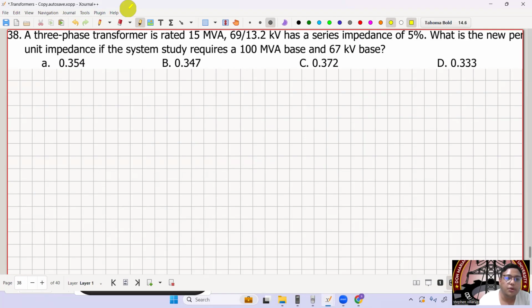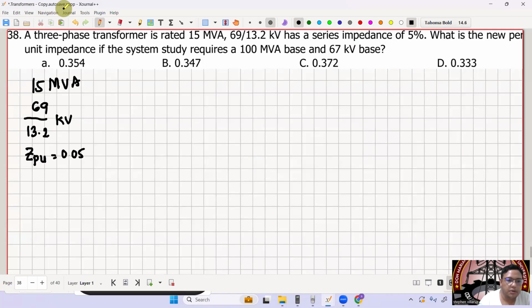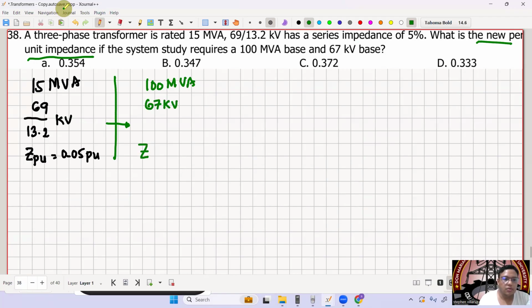Next, number 38. So a three-phase transformer is rated 15 MVA, 69 slash 13.2 kV. And your Z per unit for this transformer is 0.05 per unit. Now, ito yung tanong. What is the new per unit impedance? So, ano daw yung magiging equivalent nitong per unit impedance if the system requires you to study a 100 MVA and 67 kV base. Okay? So, ano daw yung magiging bagong per unit natin dito?